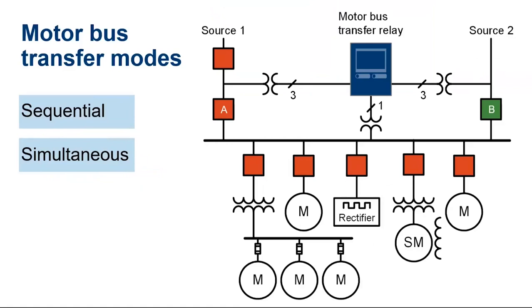There are two modes of bus transfer, sequential and simultaneous. In the sequential mode, a trip command is issued first. You get confirmation from the breaker that it is open, then you issue the close command after the normal source breaker indicates it's open. This has a slightly slower transfer time, but this method definitely eliminates the risk of closing into a fault. The other one is simultaneous motor bus transfer, and just like the name says, both trip and close commands are issued simultaneously. This may be preferred when we are doing a fast transfer. It definitely carries a risk of closing into a fault.